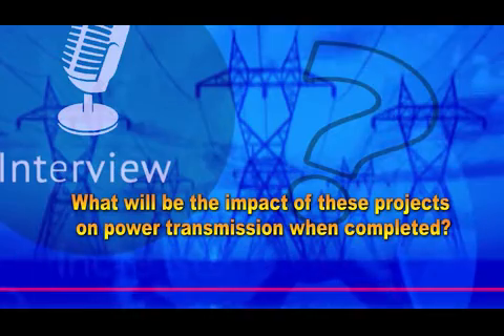Asked about the project's impact on power transmission, she said it will help improve the voltage profile within Abuja and its environment, and bring reliability up to standard. The added 132/33 kV substations will help create a ring network within Abuja, so that if there's a power outage from one of the 330 kV sources coming into Abuja, the other source will take over because of the existing ring circuit on the 132/33 kV substations around Abuja.